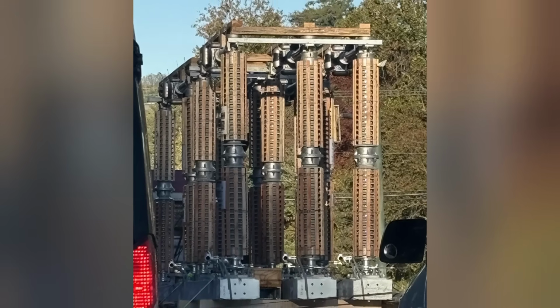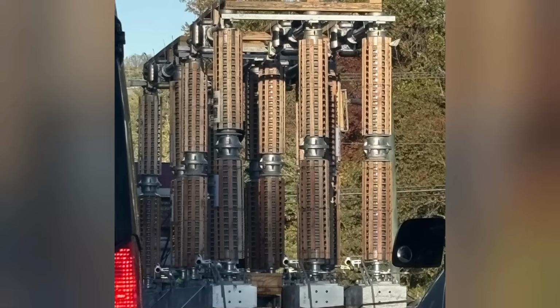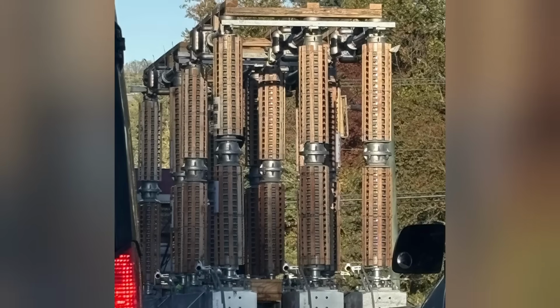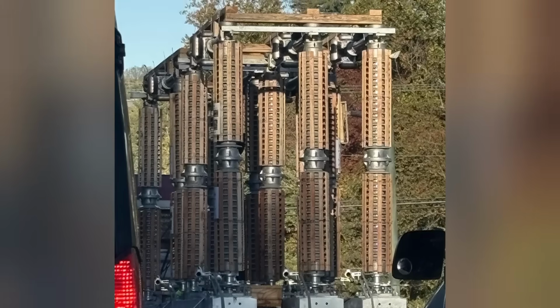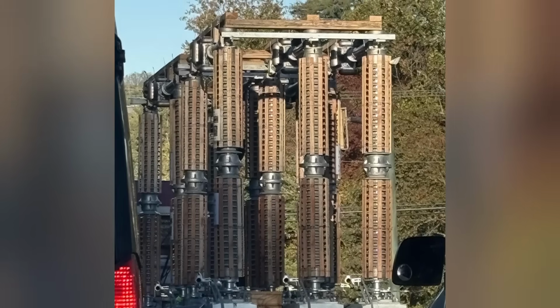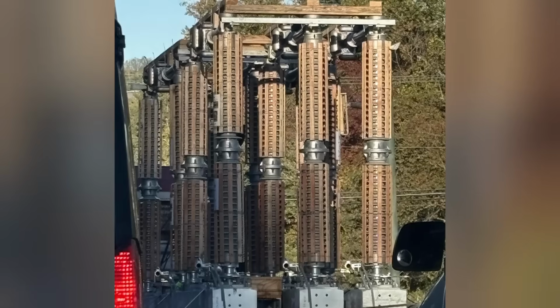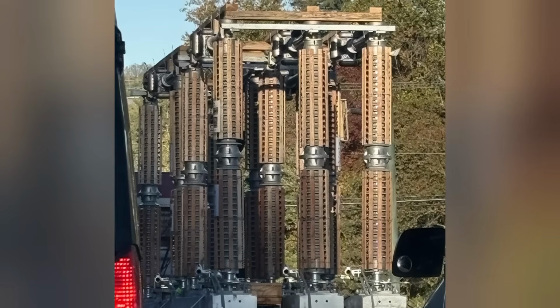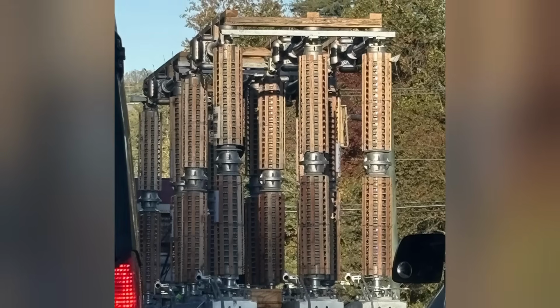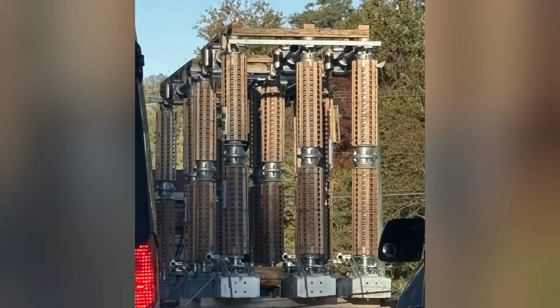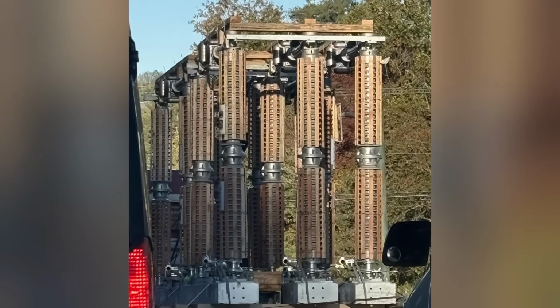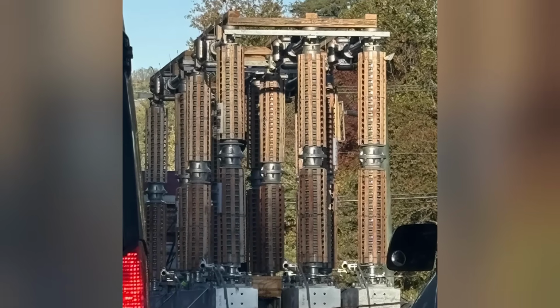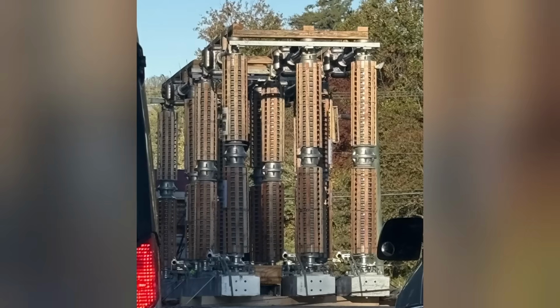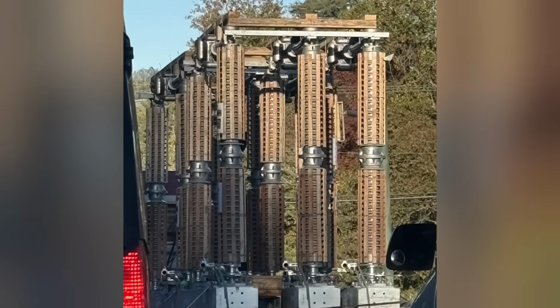This is a large, heavy-duty switch used in an electrical substation to open or close a high-voltage circuit, for example, to de-energize a transmission line for maintenance. The long ceramic or glass insulators are necessary to withstand the very high voltages. The link shows a similar Pascor brand switch with arcing horns, which are used to help extinguish the electrical arc that is created when a high-voltage circuit is opened.